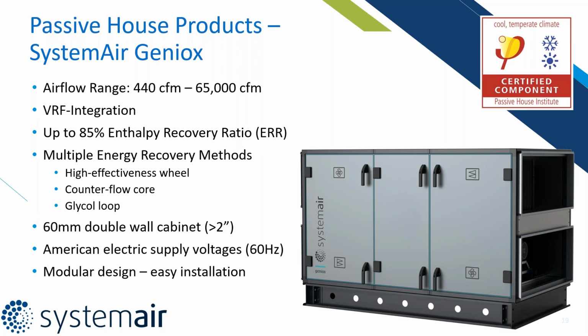But again, if you're sold on a specific VRF system, we're happy to provide the components so you can mount any VRF coil and it'll work with that. This unit will achieve up to and actually beyond 85% enthalpy recovery ratio. This will really help average out your total enthalpy recovery ratio of your building. It does that with a high effectiveness wheel, I believe it's called a Klingenburg wheel. You can use that, or you can do a counterflow core, and we can even do a glycol coil in this unit for those Type 3 or 4 exhaust.